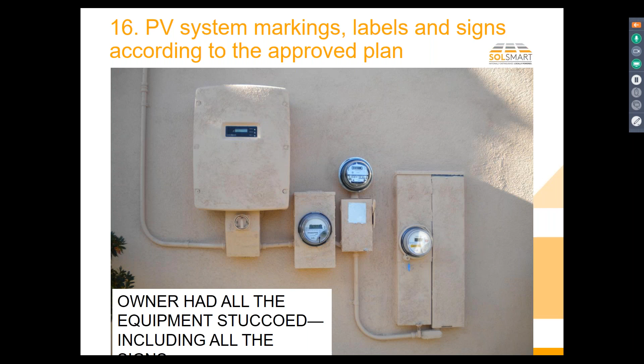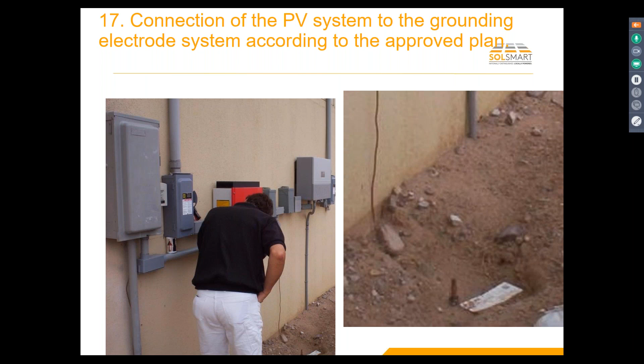Connection to the grounding electrode. So typically, we're normally connecting into the electrical panel. A lot of jurisdictions, I'm sure, around here, if you're doing anything on the electrical side of the system, are going to require you to drive another ground rod, at least have 2 ground rods 6 feet apart. Is that pretty common around here? And so that's so that if people have ground rods that are not that great, or maybe they had a water pipe ground or something like that, this is going to improve their grounding electrode system.